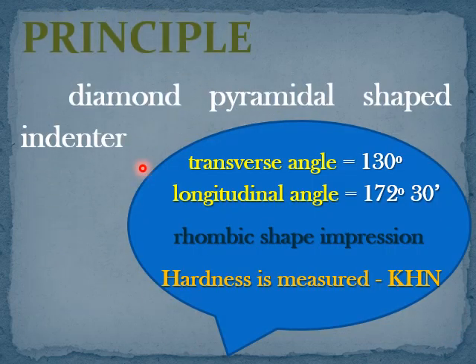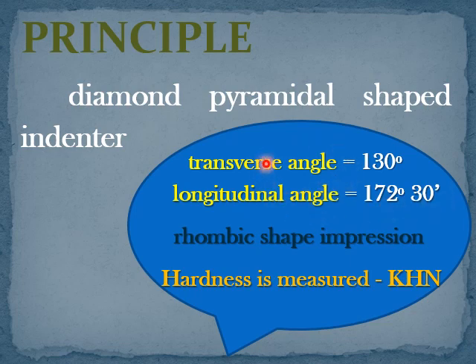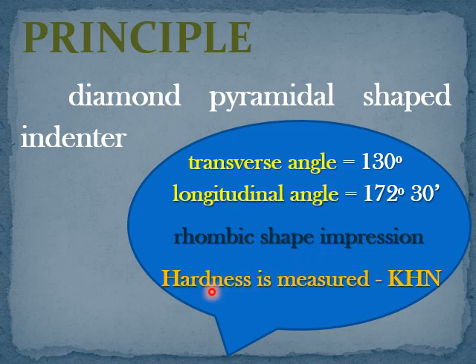The principle involved in Knoop hardness testing: a diamond pyramidal indenter is used whose transverse angle is 130 degrees and longitudinal angle is 172 degrees 30 minutes. When such an indenter is placed on the surface of the testing specimen and a known load is applied from the top surface, a rhombic-shaped impression is formed. The average diagonal length (d1 + d2) / 2 is measured from the optical microscope. Knowing the applied load and the average diagonal length d, the hardness is measured from the Knoop hardness number.